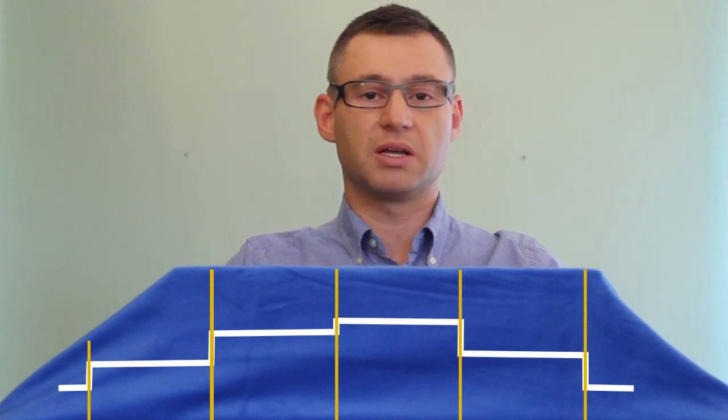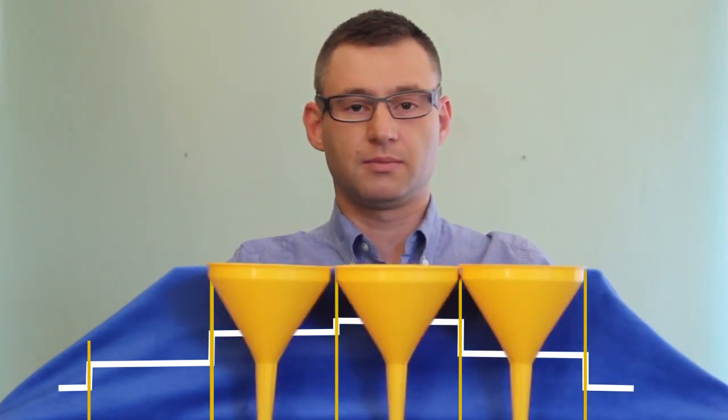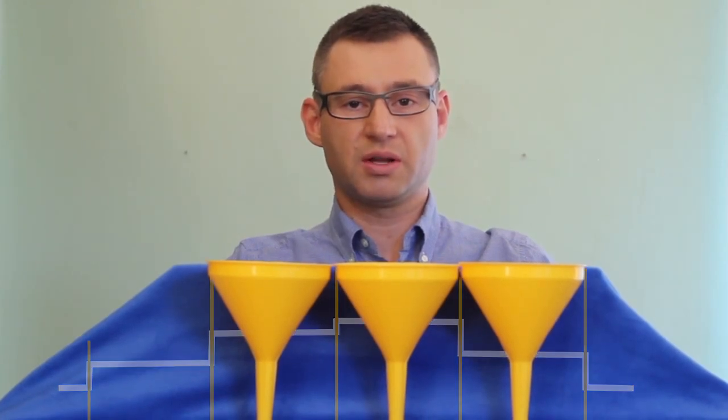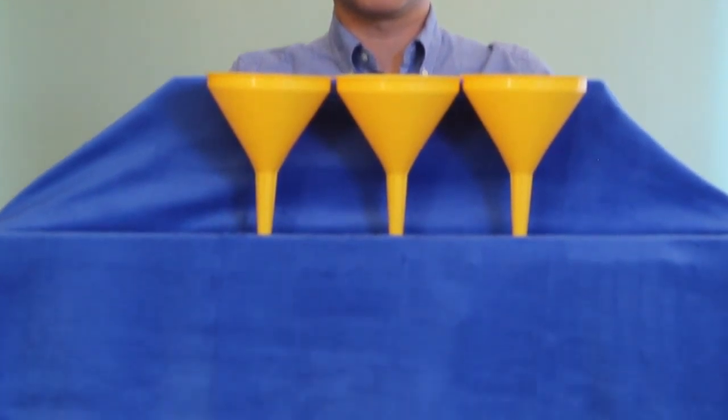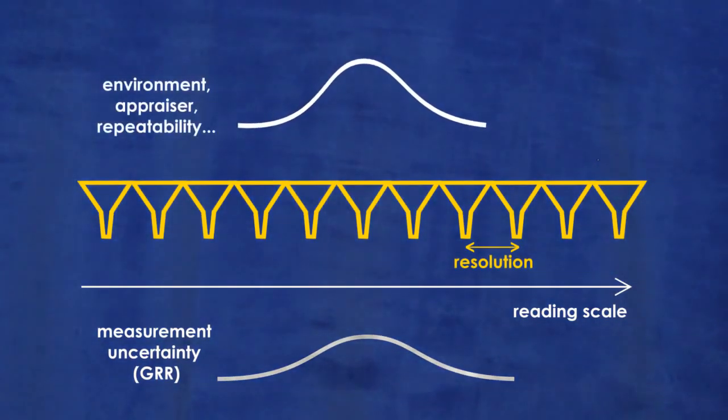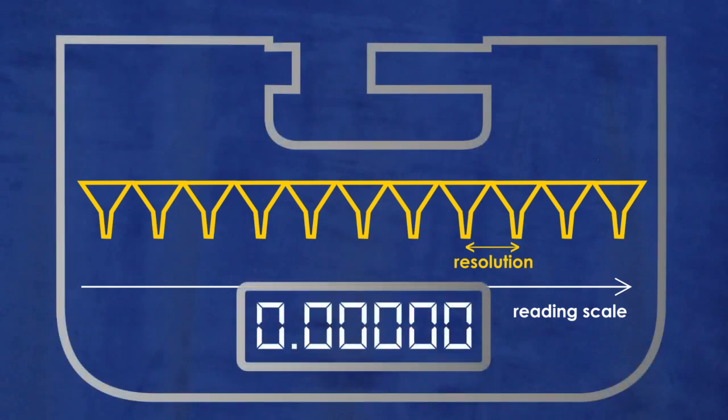Imagine the resolution bin as a funnel. The resolution has some notable properties such as it is not dependent on the measurement uncertainty, it is not dependent on the environment nor other components of the measuring process and it is not dependent on the measured part. It is solely a property of how the readout of the measuring device was designed.